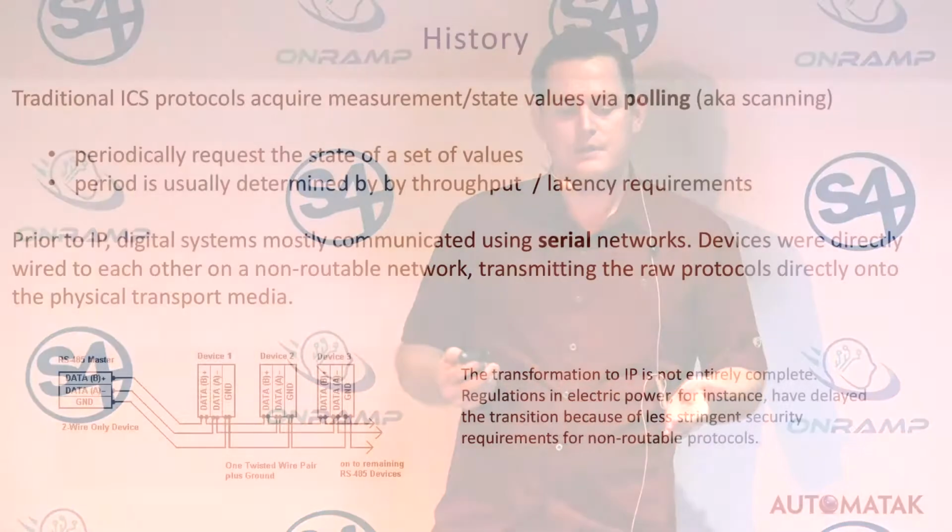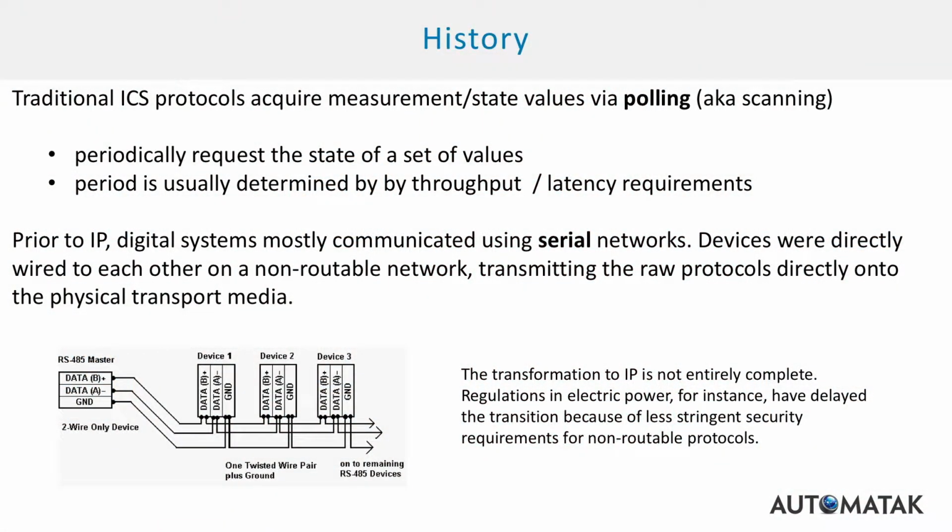So with that definition out of the way, I'll talk a little bit about history. The digitization of these protocols goes all the way back to the late 60s, 70s-ish. Originally, these protocols acquired data through a process called polling. You'll hear about polling constantly when you talk about these systems. Polling is when the component that wants to know about a measurement value periodically, on a schedule, asks that piece of equipment what's the value now, what's the value now, what's the value now, and that remote component sends back the current value, okay?